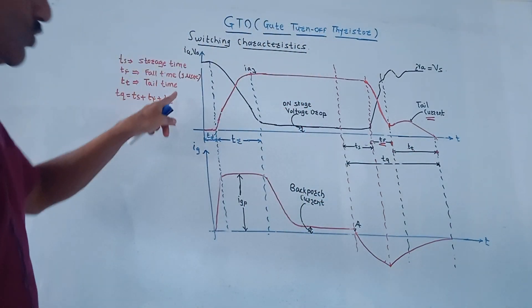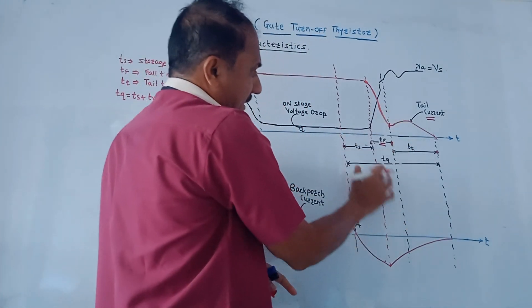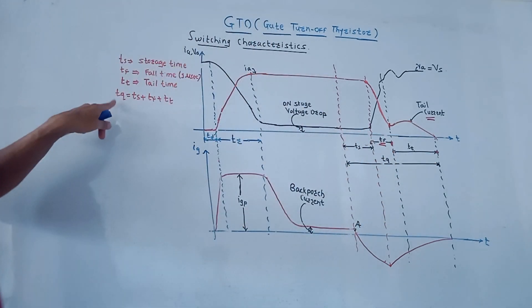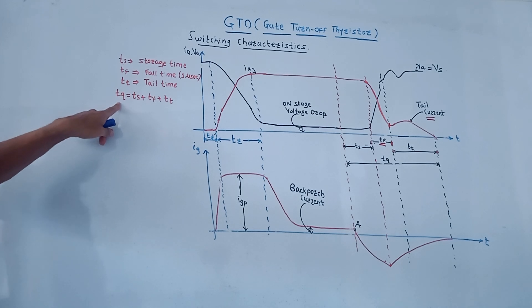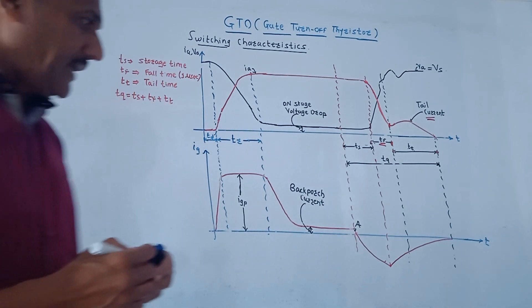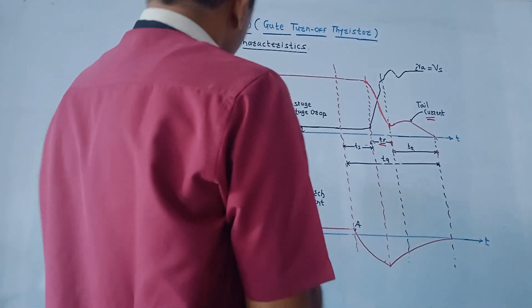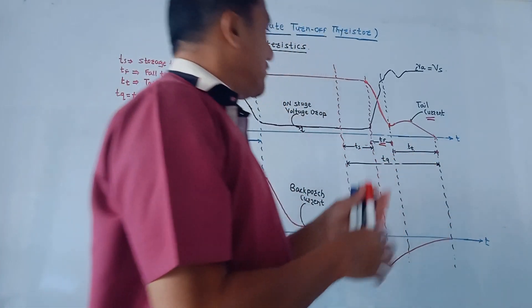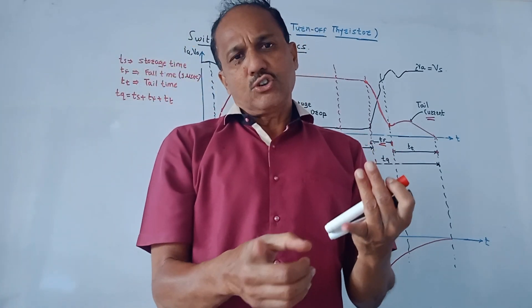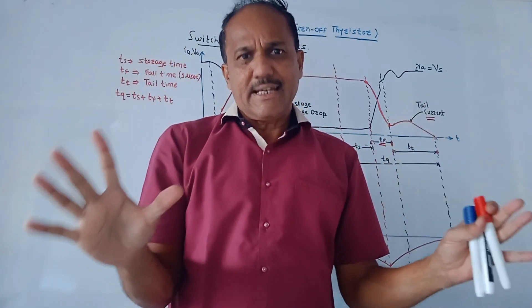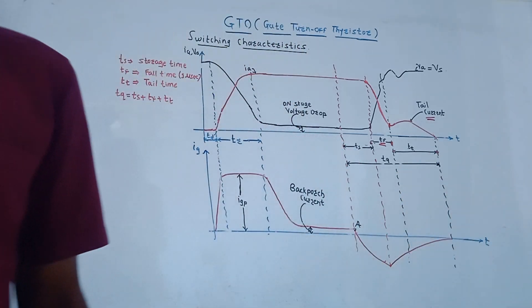The combination of all these time periods — ts, tf, and tt — represents the total turn off time period. Turn off time period is given by: tq = ts + tf + tt. Series and parallel operations of GTO are exactly the same as that of SCR.